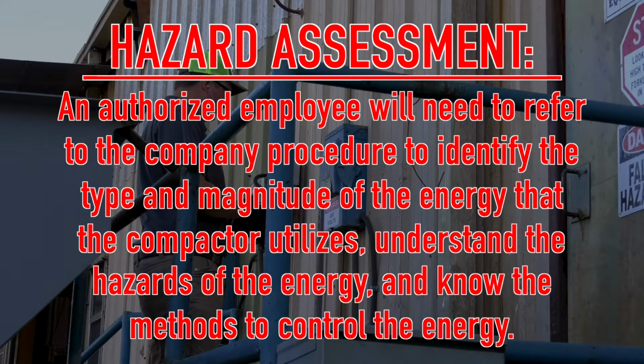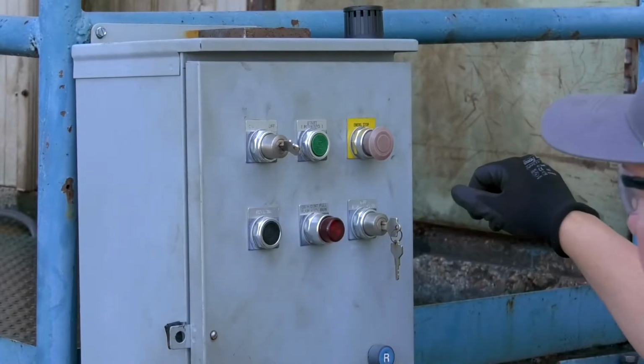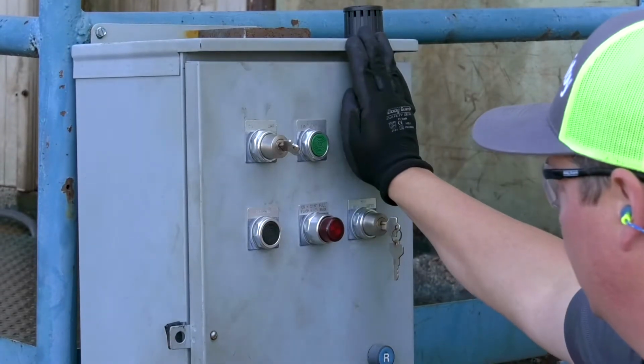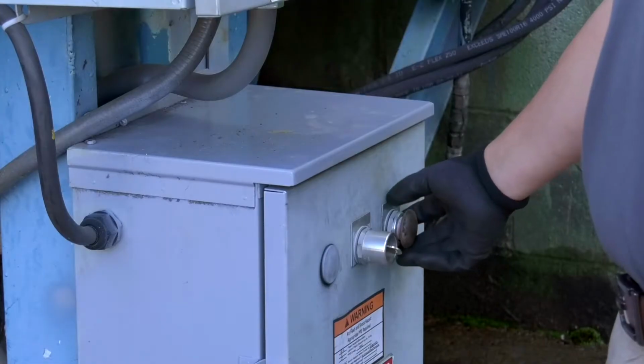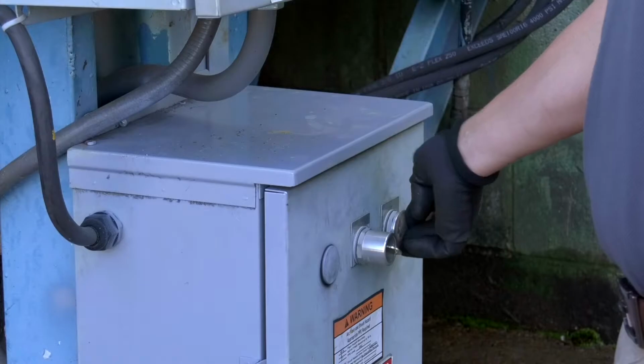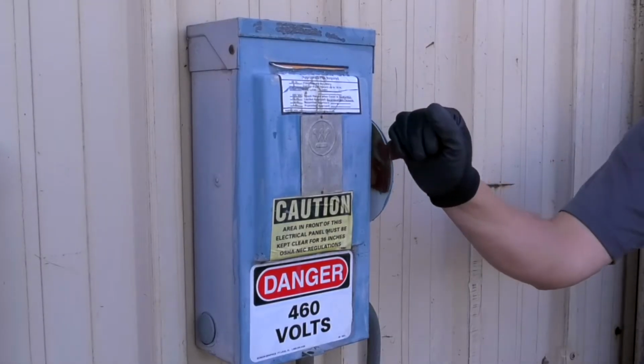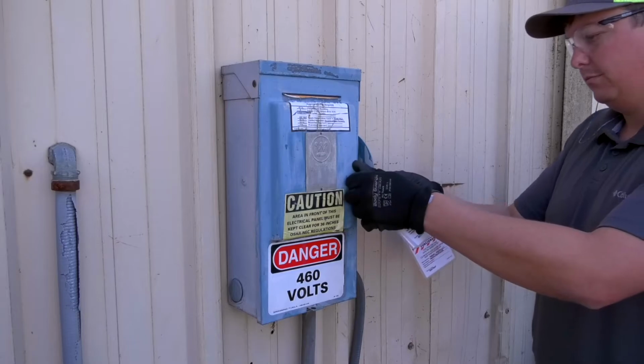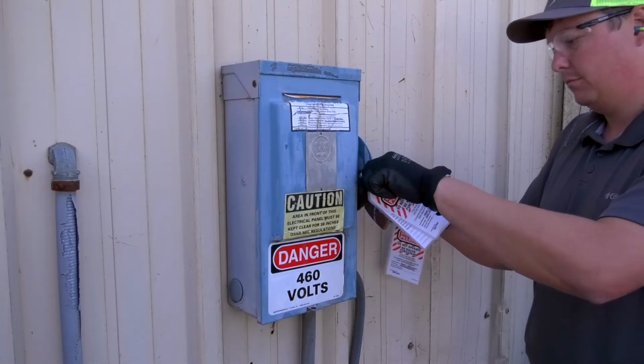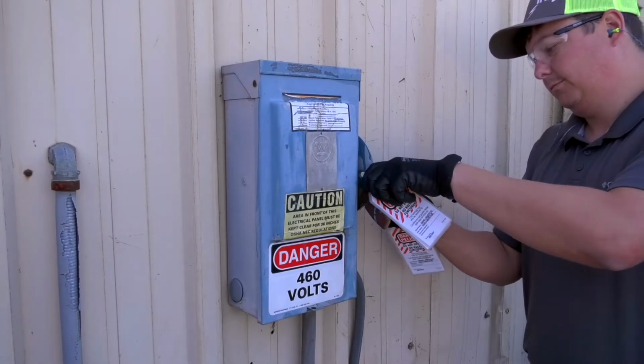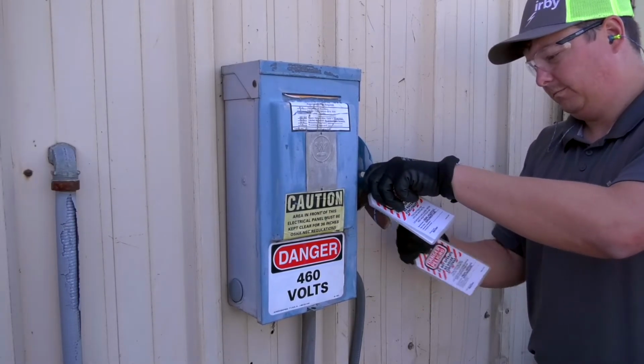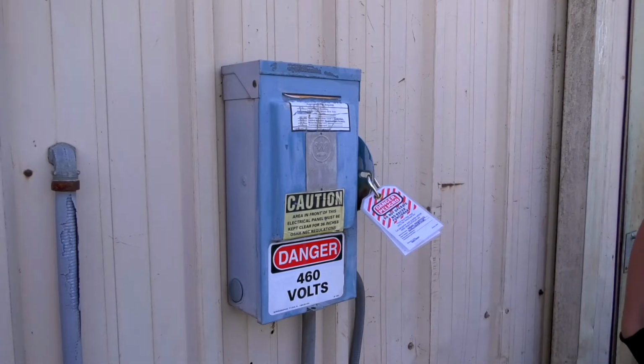An authorized employee will need to refer to the company procedure to identify the type and magnitude of the energy that the compactor utilizes, understand the hazards of the energy, and know the methods to control the energy. Next, you will need to deactivate the energy isolating devices so that the auger is isolated from the energy sources. To do this, simply shut down all power sources and move the main disconnect lever to the off position. Then lock out the energy isolating devices by placing a keyed padlock along with appropriate high visibility warning tag on the disconnect lever. When finished, take the padlock key with you.